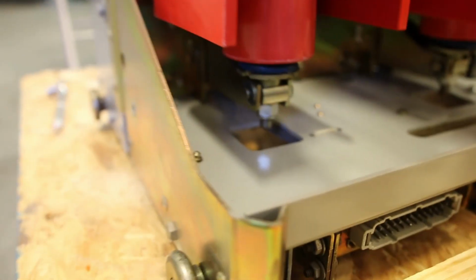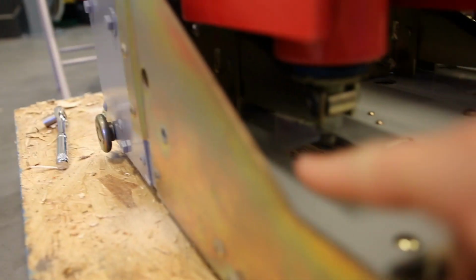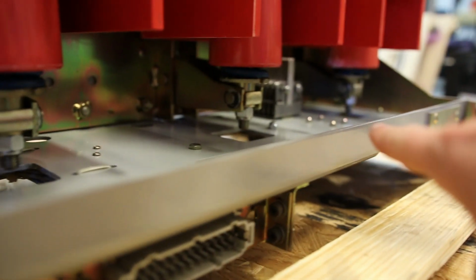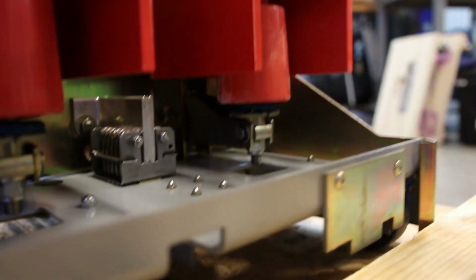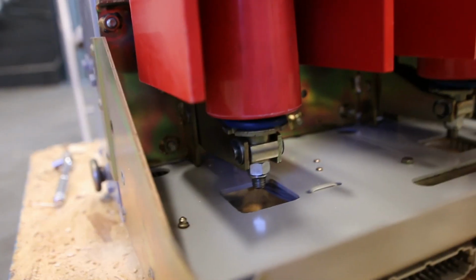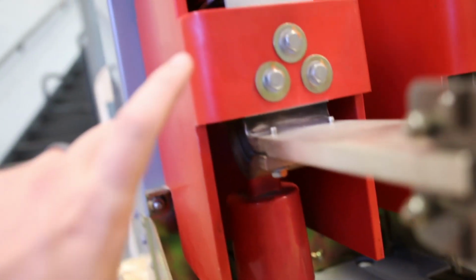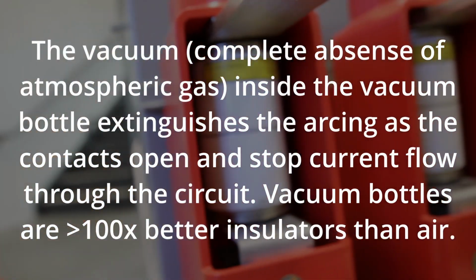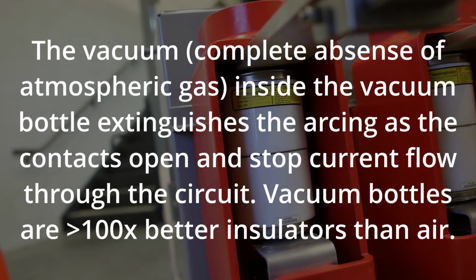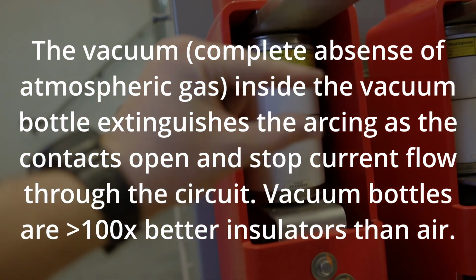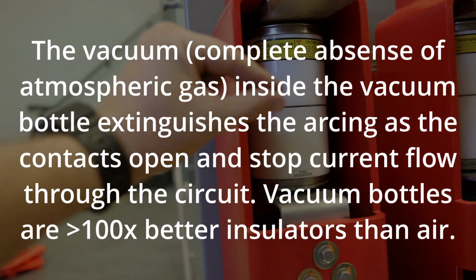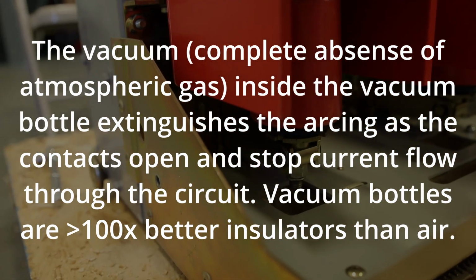And when the breaker operates, when it closes, that's that same rod that comes out the front for each phase. Got one on the other phase as well, and those push this whole assembly up. This is the vacuum bottle in the back. Let me get that in focus there. That's the vacuum bottle. The contacts in there only move a couple thousandths of an inch, not a whole lot. That rod doesn't have to move very much in order for the contacts to open or close.